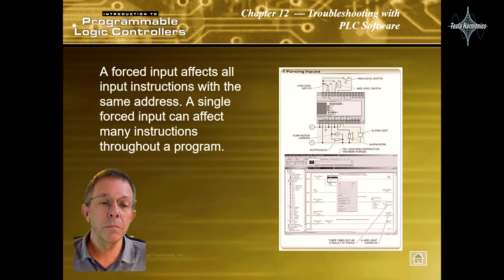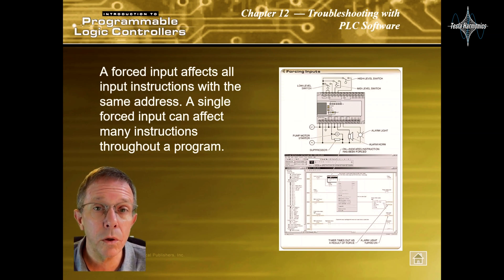A force input affects all input instructions with the same address. A single force input can affect many instructions throughout a program.